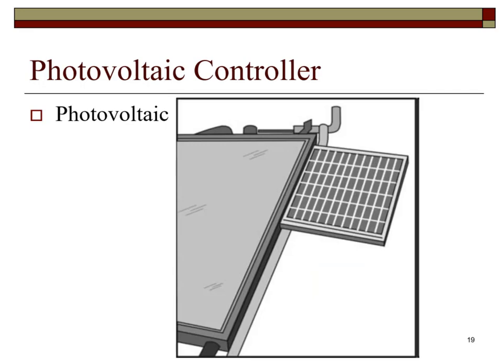The system shown differs from the direct pump system in that energy to power the pump is provided by a photovoltaic panel. The PV panel converts sunlight into electricity, which in turn drives a direct current pump. In this way, water flows through the collector only when the sun is shining. The DC pump and PV panel must be suitably matched to ensure proper performance. The pump starts when there is sufficient solar radiation available to heat the solar collector. It shuts off later in the day when the available solar energy diminishes.